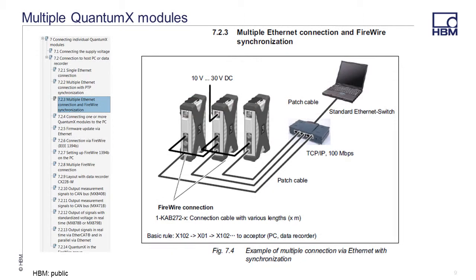The most common method of connecting multiple QuantumX modules via Ethernet is to use the FireWire connection for synchronization and power distribution. Each module requires an Ethernet connection to a switch and then Ethernet from the switch to your PC. The Ethernet cable is only providing data, so synchronization is provided by having a FireWire cable connection between every QuantumX module. The FireWire connection can also provide power for every three modules, with one of those modules having a power supply connection.